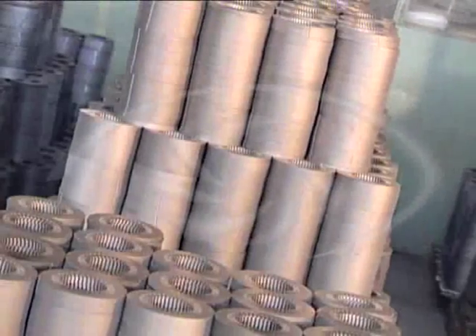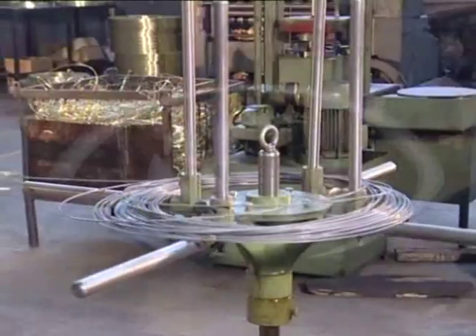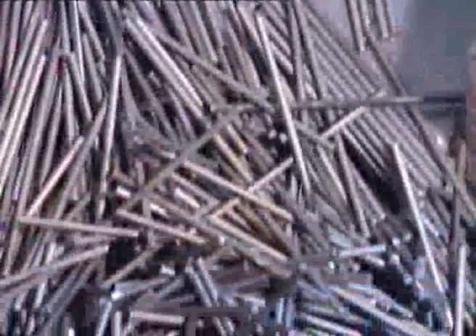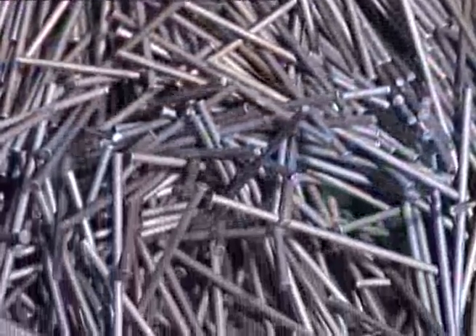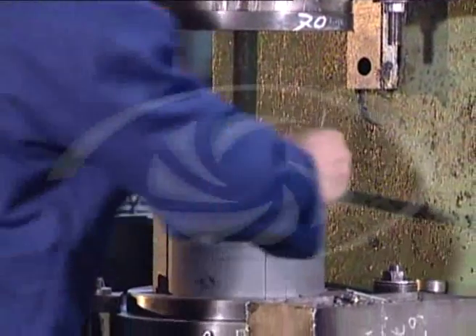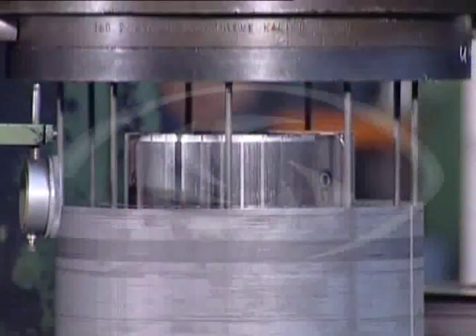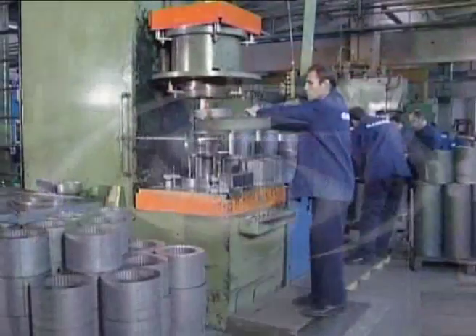After the laminations are punched, they are submitted to a treatment process to ensure their electromagnetic characteristics where necessary. The rivets produced with this machine is a small example to show that all parts in the electric motor are manufactured in-house. The stator and rotor packs are formed by riveting the punch lamination steels of 0.5 thickness, which are then submitted to the winding department for winding process.